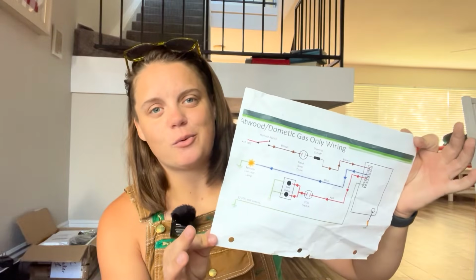Unlike testing for volts DC, where you put one probe on a screw and poke around with the other, when testing for continuity you take your probes and put them on either side of an element in the circuit. If you're a little overwhelmed, don't worry. I'm going to walk you through step by step where your probes go for each part of this. You've got this, it's really not that difficult. On to testing your water heater.